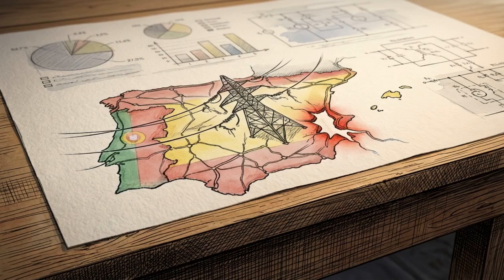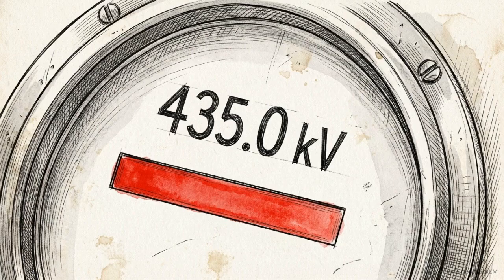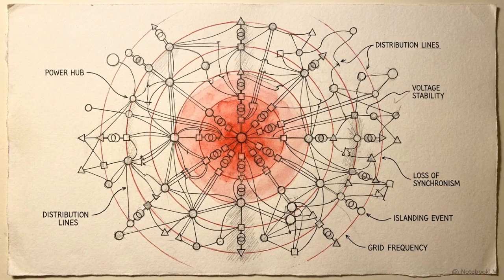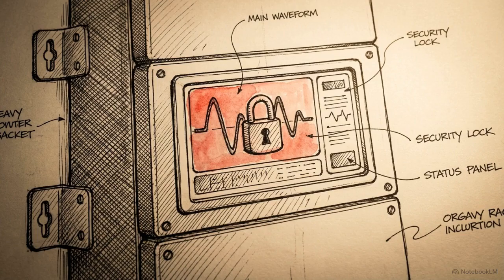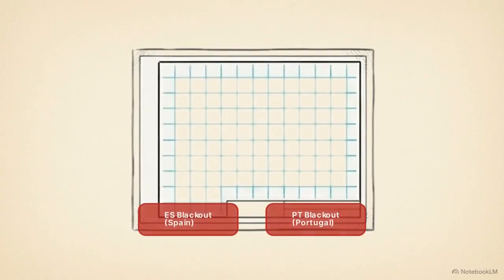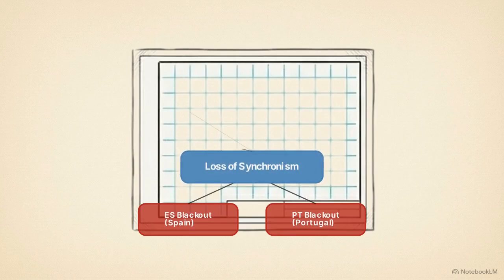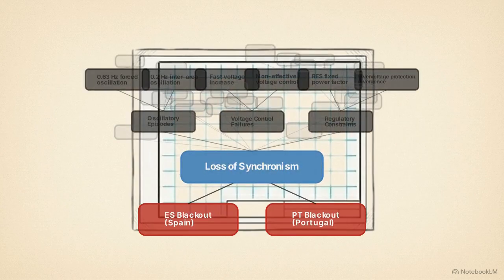To understand the failure, we have to look past standard power shortage metrics and examine the physics of dynamic voltage control in the final seconds before the blackout. The investigation revealed that the root cause of the blackout was a failure of dynamic voltage control, triggered by fixed power factors in inverter-based energy resources. This is the official ENTSO-E root cause tree. We will use it as our map, focusing on the final outcome, the loss of synchronism.